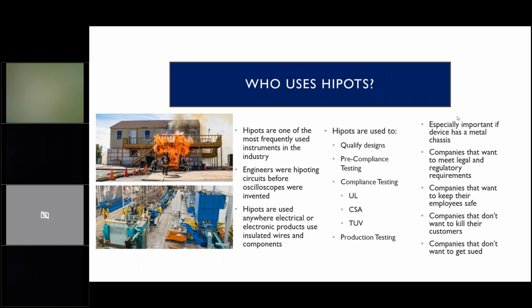So metal chassis devices are supposed to have a third wire on the power plug for ground, and it's important that that wire is hooked up and that it's sufficient gauge to handle the currents in case there's a big shock. Okay, so if there is a short inside a device like this, it goes to ground, and the ground shunts that current off to earth ground. Okay, that's how it makes it safe. So HIPOTs, especially if they have ground bond capability, are really good for testing these things.